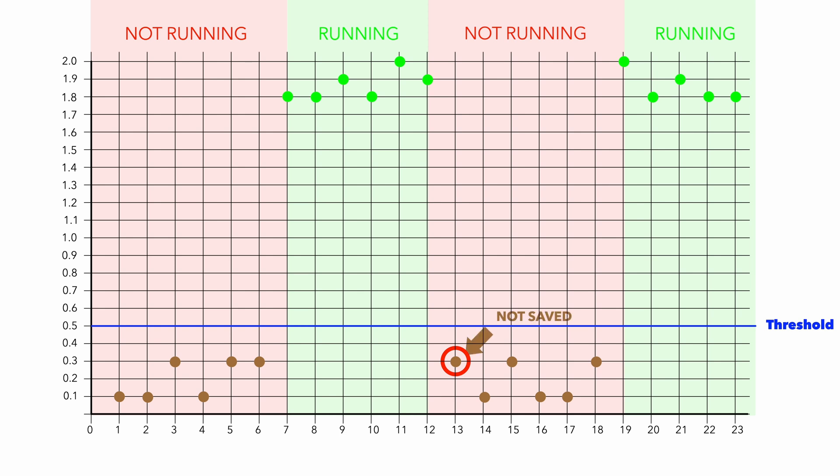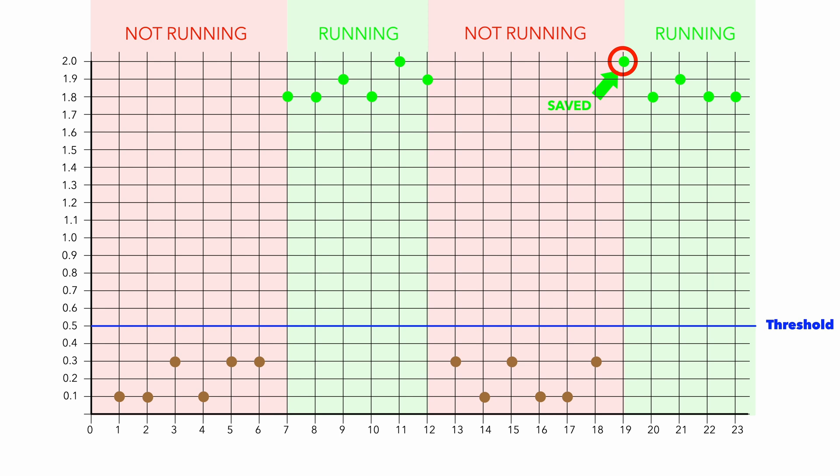And also, all other values below threshold after this one are not saved. Next value above threshold is saved, and it will cause this. Trend of values will look like there is stable high value on the machine, which is not true.